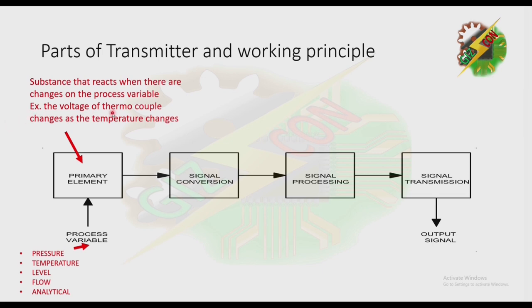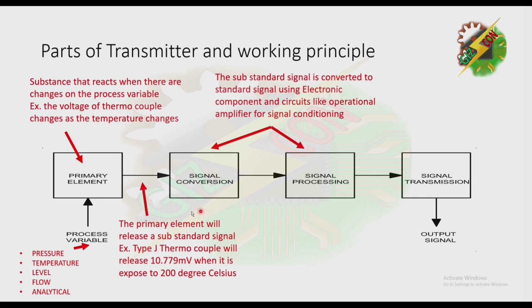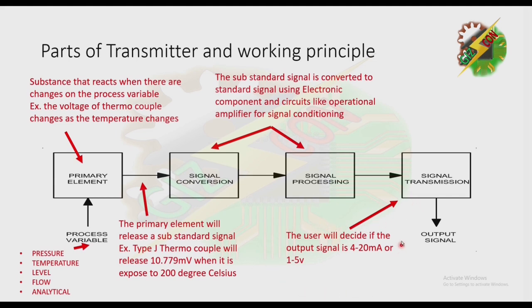For example, a type J thermocouple will release 10.779 millivolts when it is exposed to 200 degrees Celsius. Then, in the signal conversion and data processing stage, the substandard signal is converted to a standard signal using electronic components and circuits like operational amplifiers for signal conditioning. The 10.779 millivolts is now converted to a standard signal. For signal transmission, the user decides if the output signal is 4 to 20 milliampere or 1 to 5 volts.